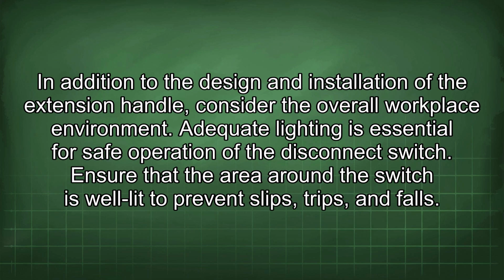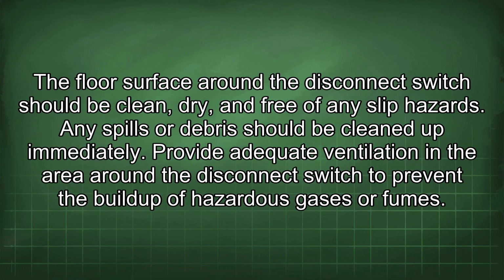In addition to the design and installation of the extension handle, consider the overall workplace environment. Adequate lighting is essential for safe operation of the disconnect switch. Ensure that the area around the switch is well lit to prevent slips, trips, and falls. The floor surface around the disconnect switch should be clean, dry, and free of any slip hazards. Any spills or debris should be cleaned up immediately. Provide adequate ventilation in the area around the disconnect switch to prevent the buildup of hazardous gases or fumes.